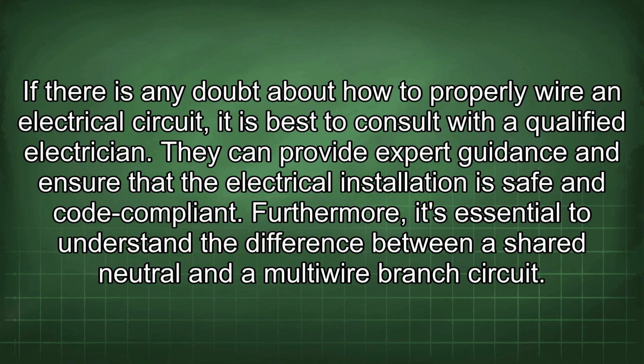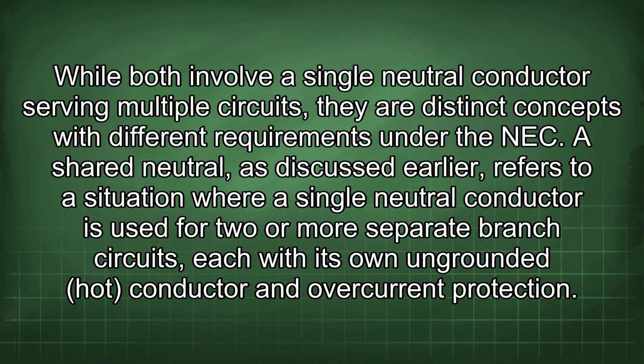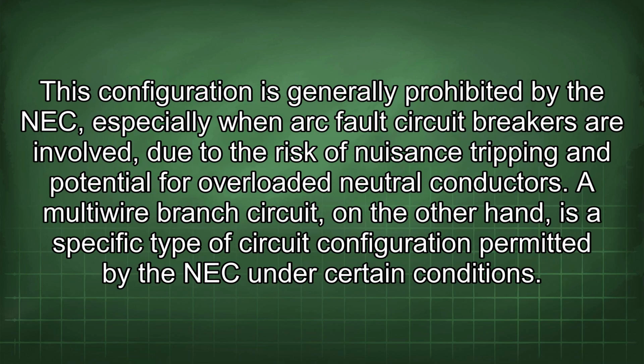Furthermore, it's essential to understand the difference between a shared neutral and a multi-wire branch circuit. While both involve a single neutral conductor serving multiple circuits, they are distinct concepts with different requirements under the NEC. A shared neutral, as discussed earlier, refers to a situation where a single neutral conductor is used for two or more separate branch circuits, each with its own ungrounded hot conductor and overcurrent protection. This configuration is generally prohibited by the NEC, especially when arc fault circuit breakers are involved, due to the risk of nuisance tripping and potential for overloaded neutral conductors.